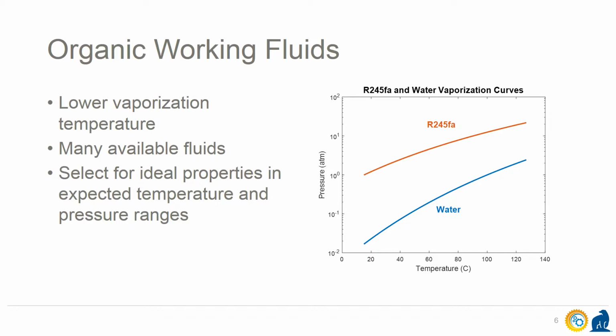While these organic working fluids make the process possible at low temperatures, there are still some issues. The lower temperature means there is less energy available per unit volume. This means the power needed to pressurize the working fluid makes up a larger portion of the power you get out. If the temperature gets too low, it may just barely be able to keep itself going with no power for anything else, no matter what fluid is used. The model will help us find that level and tell us how much power we have to spare.